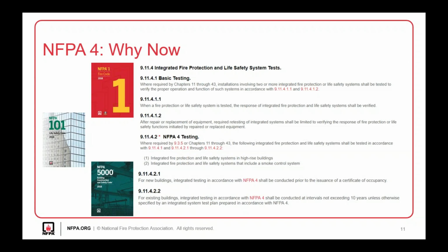There was a lot of discussion during the revision cycle of the 2018 edition of these codes about whether NFPA 4 integrated testing should be required for all occupancies. Prior to a temporary interim amendment (TIA) to NFPA 101 and 5000, the code actually required integrated system testing for all occupancies, not just confirming output. During discussion, it was determined they'd start with higher risk occupancies like high-rise buildings and smoke control systems. So I wouldn't be surprised if more occupancies get added to this list in future revision cycles.